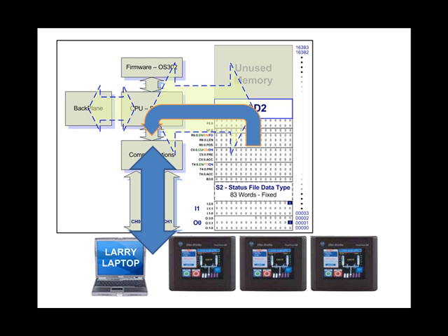The characteristic of this type of controller that really identifies it as having naked data is that you can plug another PLC into one of these COM ports and by means of a message instruction read anything from this memory and write anywhere into this memory without this controller needing to give the other controller permission.